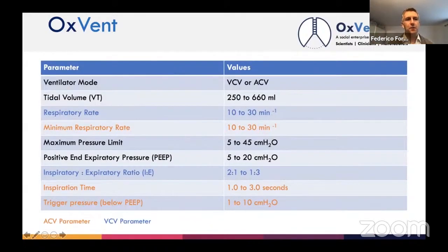And this is just an overview of what we can set with this ventilator. There are two ventilator modes. One is where we determine the volume that is delivered at each breath, and it is delivered at a set respiratory rate. So there's a set number of breaths delivered per minute. That is in contrast with the other option, which is assist control volume. In that option, an inspiratory effort from the patient, which is measured in the system as a drop in the pressure, is what triggers the delivery of a breath. And so this ventilator offers both ventilation modes. And then the ranges for the tidal volume, the respiratory rate, and pressures that are limited.